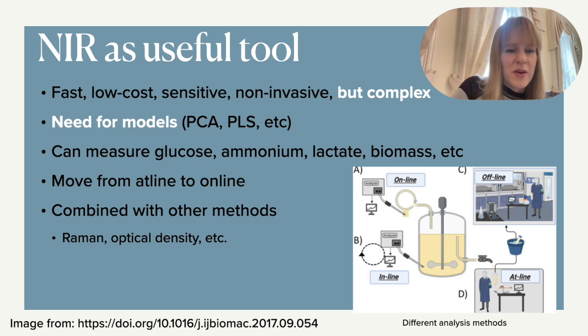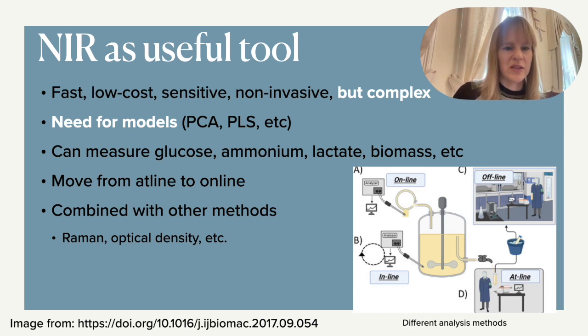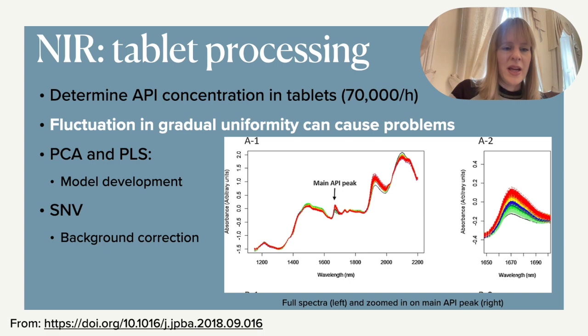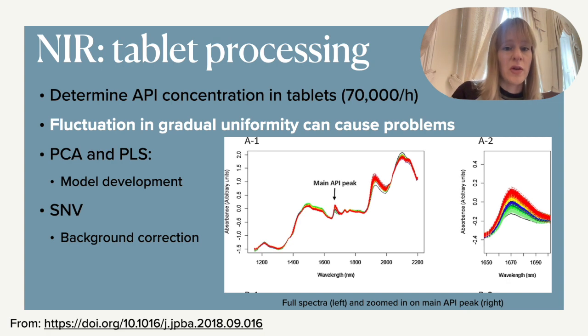NIR is often combined with other tools. Raman is quite complementary because it looks at similar peaks but can identify other compounds. For biomass you might combine results with something like optical density. NIR was used for tablet processing because it is a non-destructive technique — it's so fast that you can process around 70,000 tablets per hour, making it very good for quality control.